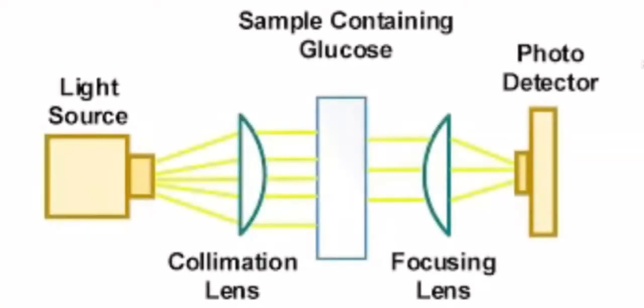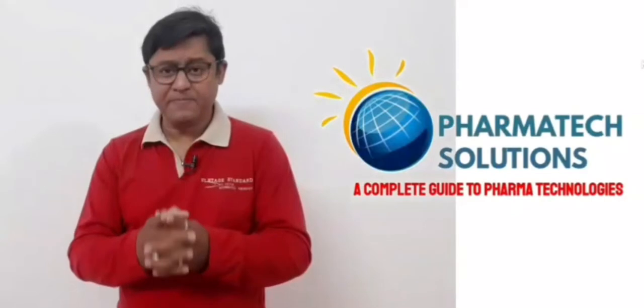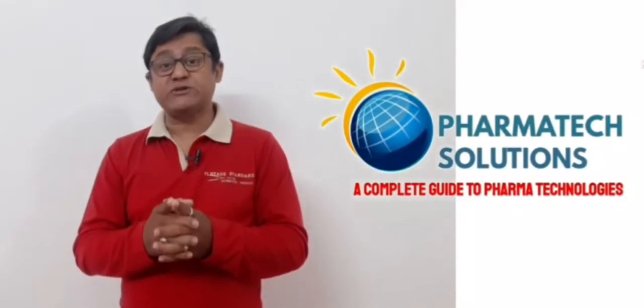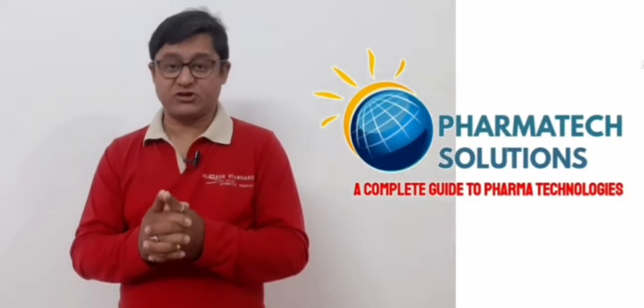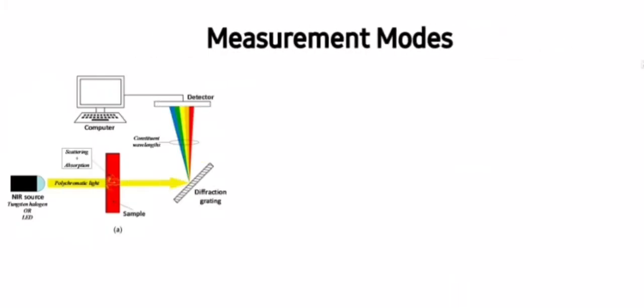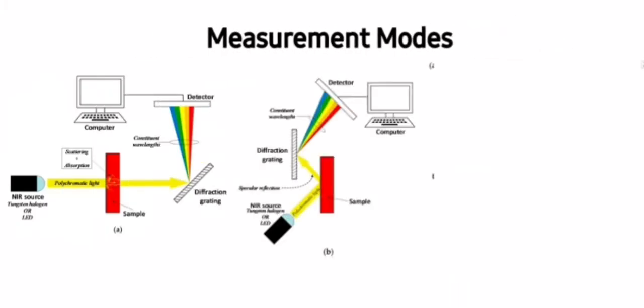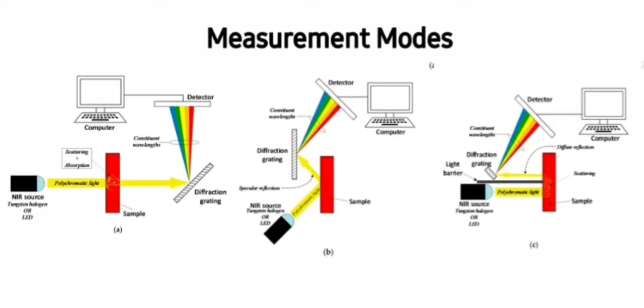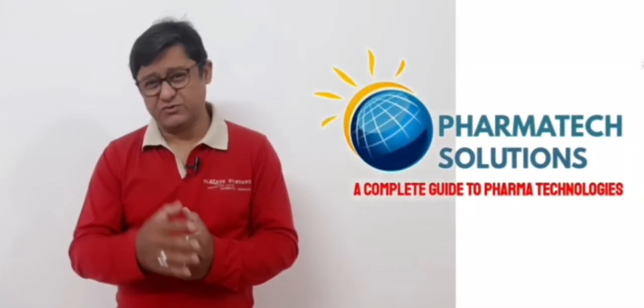Here, the light interacts with the sample and the detector measures the transmittance and the absorbance. Now this technology uses three basic measurement modes: transmittance, reflectance which includes diffuse reflectance, and interactance. However, all three work on the same core technology, that is dispersive spectrometry.